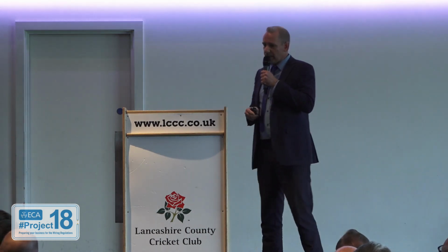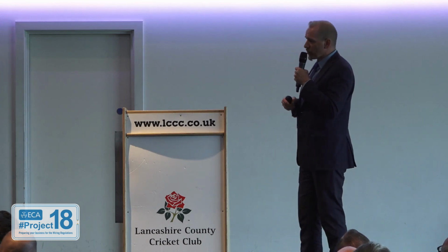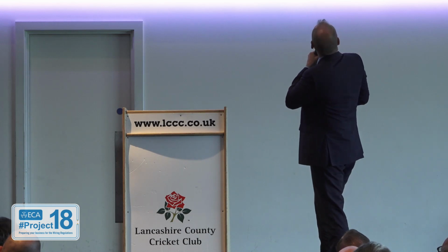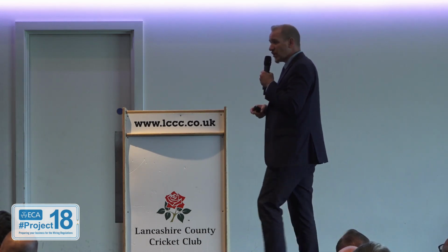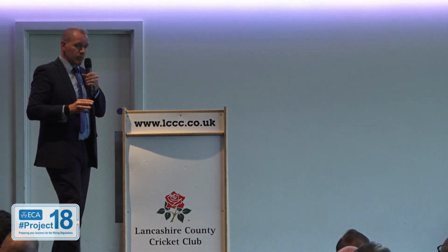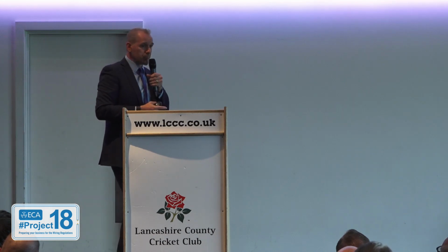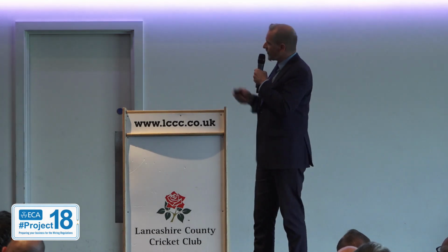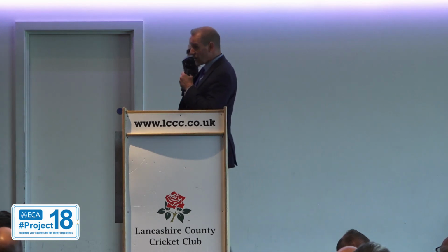So, just wrapping up that little bit, section 527, which follows after the one we've just looked at, says that the risk of spread of fire shall be minimised by selection of appropriate materials. What are appropriate materials? The stuff that we've just been talking about, really. Getting away from the plastic and utilising metal containment systems and cleats and clamps and that kind of thing, because that's the thing that's going to put us in complete alignment with the regulation. So it's making sure that we have all the necessary resistance to flame propagation and all of that type of thing within those standards there.